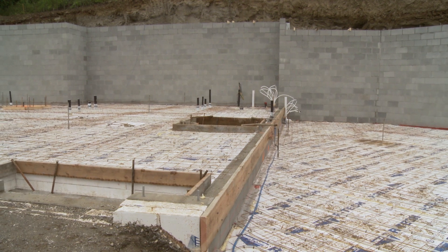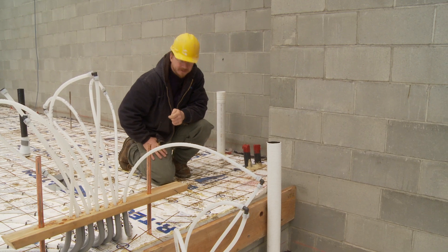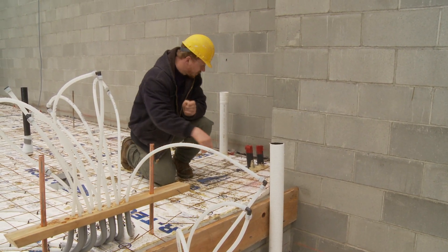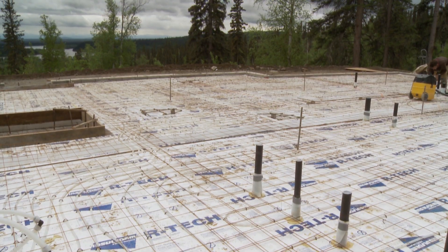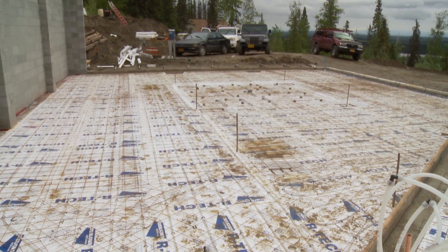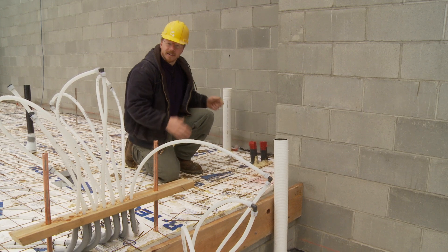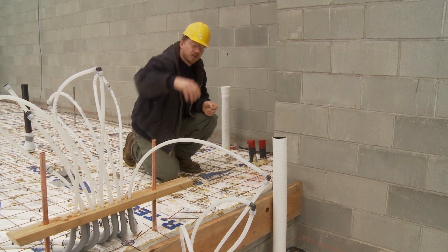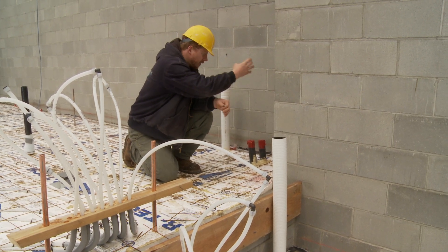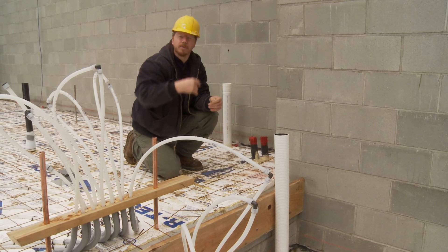This house has a stepped floor system with a concrete bearing wall dividing the floor in half. Since the tubing couldn't be run through the floors, we've got two separate runs of tubing — a loop running around the perimeter of the upper floor and the same run of tubing running around the lower floor. The lower floor system meets at a collection point here, and the upper floor meets here. The runs of tubing are divided roughly in half, and then the radon fan will connect to both pipes here in a riser, drawing roughly equally from both floor systems.